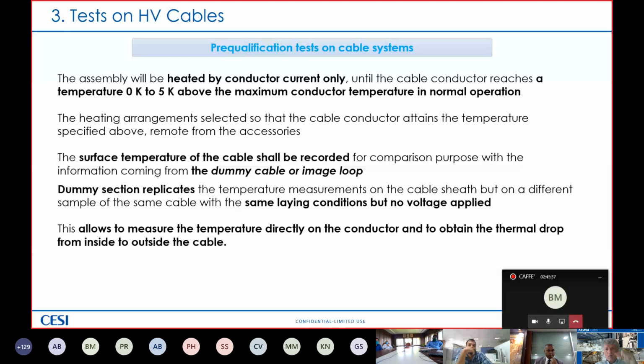We have the same current circulating. We measure on the conductor, we measure on the cable sheath, so we gain the so-called thermal drop. That is the difference between the temperature on the cable sheath compared to the temperature on the cable conductor. This difference is named thermal drop, and we have the measurement coming from the real cable that is under voltage, where we can only measure the temperature on the cable sheath. This temperature should be very close one to the other, and we use this thermal drop in order to increase or reduce the current circulation in order to be in the tolerance of 0 to 5 Kelvin for the maximum conductor temperature.